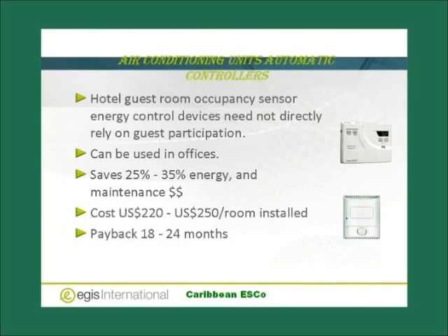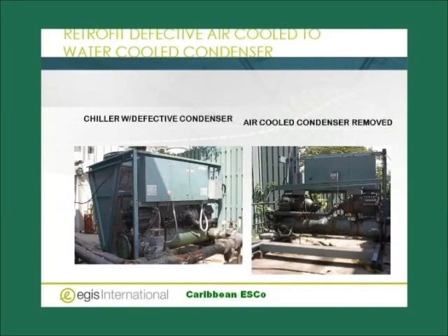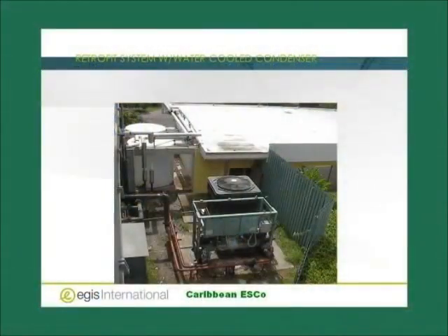We did a job at a particular high-profile company in Jamaica where we converted the air conditioning system from being cooled by air to being cooled by water. So retrofits can take place on air conditioning systems that will make a big difference. So we had a job where we converted the same unit that you see on the left, which is on the right without the air cooling section. And we then converted it to a water cool section. Yes, this here is a water cool section. We converted this unit, the same one, to water cool.